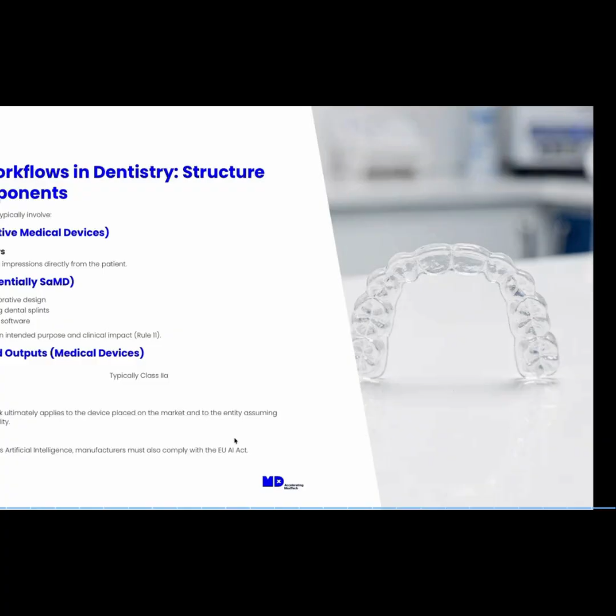And the fact that some of these softwares or algorithms have AI incorporated means they need to comply not just with the MDR, but also with the EU AI Act. As a practical tip, the AI Act does not expect these devices or softwares to have two different sets of technical documentation, but it expects that the requirements from the AI Act are incorporated into the MDR technical documentation. This may include real-world testing data, algorithm validation, and transparency and data governance aspects, just to complete the requirements that are specified by the GSPRs in Annex 1 of the MDR.